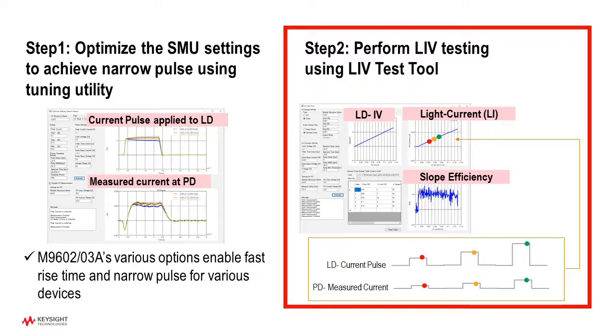Step 2: Perform LIV test with the SMU settings optimized using the LIV test tool. This tool helps to perform the LIV test and plot a graph. The graph is used to evaluate the linearity of the optical output power with different input current to identify the kink.